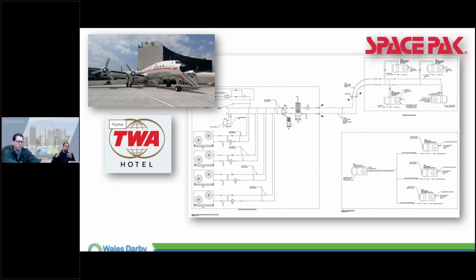Believe it or not, the contractor that won the bid for this job saw the layout, didn't know anything about air to water, and actually tried swapping this whole job to DX refrigerant, and it was not going to happen because they could not do the long lengths with refrigerant lines. They would have had to run 4 condensers, 4 runs of pipe, it would have been a nightmare. So the only thing that made sense here was air to water. So it was a good comment.